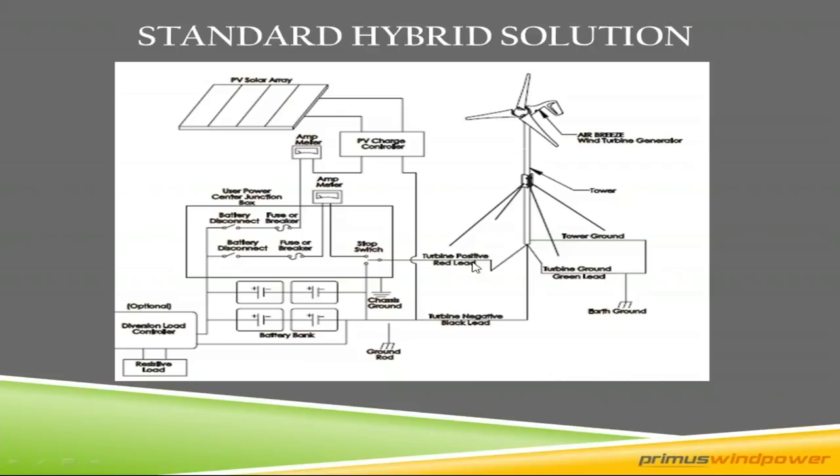There's an optional diversion-capable charge controller you can use, like a Morningstar TriStar 45 or a C40 made by Schneider — formerly Xantrex — and then you can dump that extra energy into a resistive load like an air heater or water heater. On the turbine side, you turn up the potentiometer screw to a higher voltage so it continues to push amps. Any excess charge above the regulation voltage set point would go to the diversion charge controller and be diverted to that dump load. Wholesale Solar provides all those components.